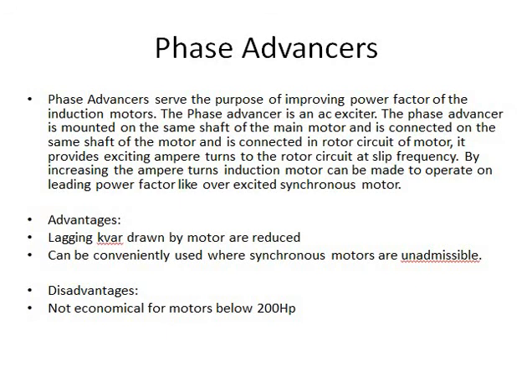By increasing the ampere turns, the induction motor can be made to operate on leading power factor like overexcited synchronous motors. Further, these phase advancers may be adjustable or non-adjustable. It's a source of reactive power connected either to certain junction points in an electric network or directly to the load terminals. It is used to compensate the phase shift between the voltage and the current, the objective being improvement in power factor. Phase advancers make it possible to adjust or maintain the voltage in the network, lower the power losses, and increase the capacity of the electric system.